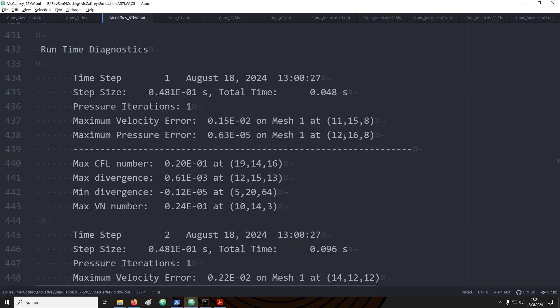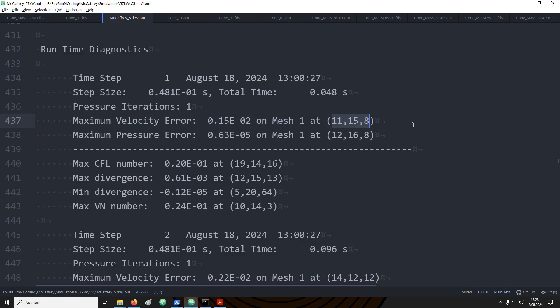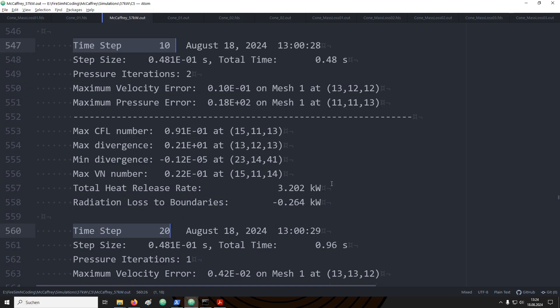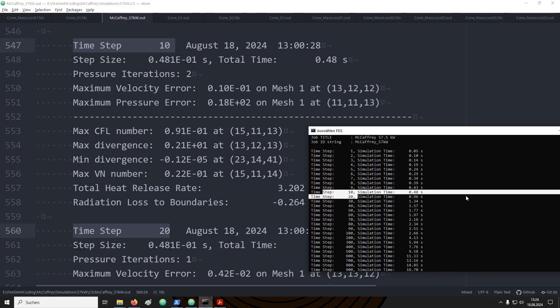At the end of the file is an overview over the runtime diagnostics. Here you get information for each time step, for example, the velocity errors and how many pressure iterations have been conducted. FDS provides you with information where specific errors are happening inside the domain. For example, let's focus here on the maximum velocity error. It tells us that at time step 1, the maximum velocity error was happening in mesh 1, and it gives us a specific cell location in x, y and z coordinates.